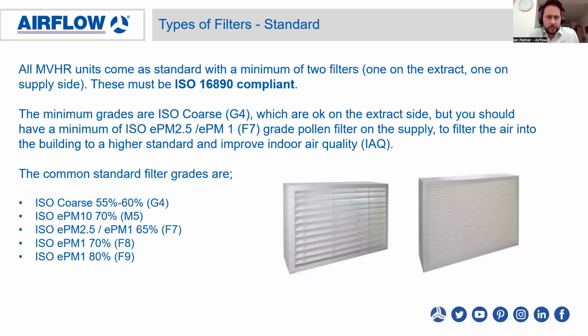So going on to the filters, I mentioned them just then when we were going through the anatomy of the units. All MVHR units come as standard with a minimum of 2 filters, one on the extract, one on the supply, and these must be ISO 16890 compliant. The minimum grades are ISO coarse, which are the most common. These are okay on the extract side, but you should have a minimum of ISO ePM2.5 or ePM1, which is also known as an F7 grade pollen filter, on the supply, to filter the air into the building to a higher standard and improve indoor air quality.